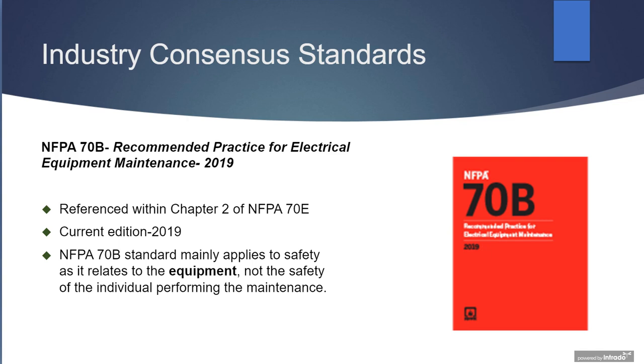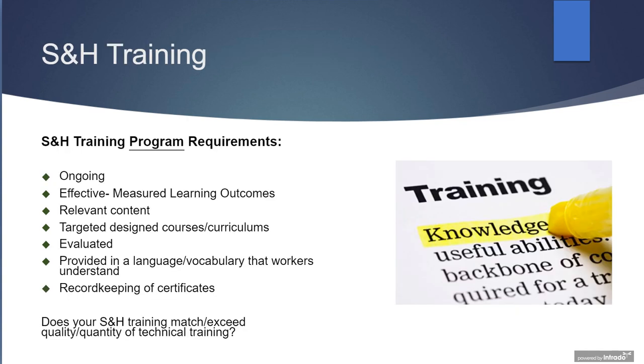Here's another NFPA document referenced within Chapter 2: the NFPA 70B, Recommended Practices for Electrical Equipment and Maintenance, currently on the 2019 edition. While Chapter 2 of the NFPA 70E relates specifically to personnel safety, the 70B mainly relates to safety as it applies to the equipment—both are very important. Your go-to documents should be the NFPA 70E and the NFPA 70B; I don't think anybody working in electrical safety should be without these.